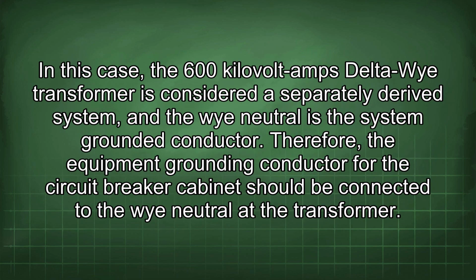In this case, the 600 kVA delta-Y transformer is considered a separately derived system, and the Y neutral is the system grounded conductor. Therefore, the equipment grounding conductor for the circuit breaker cabinet should be connected to the Y neutral at the transformer.